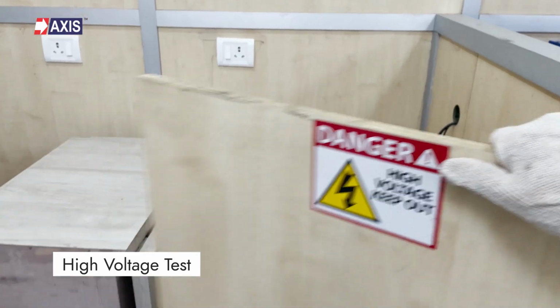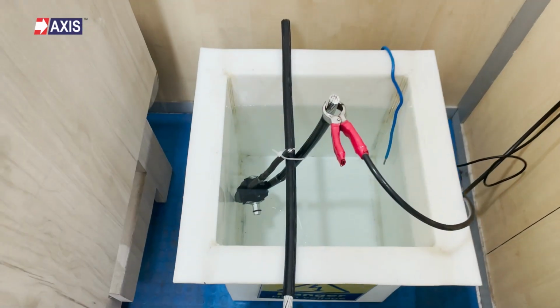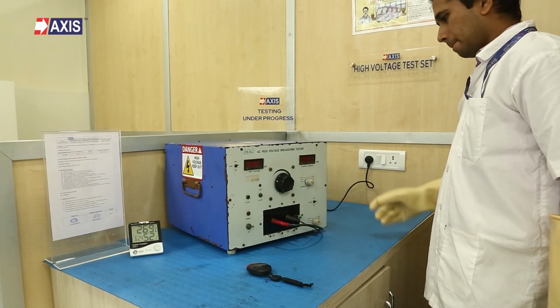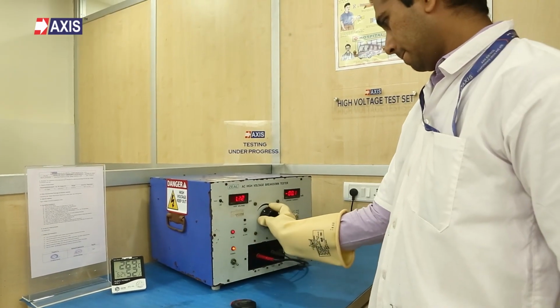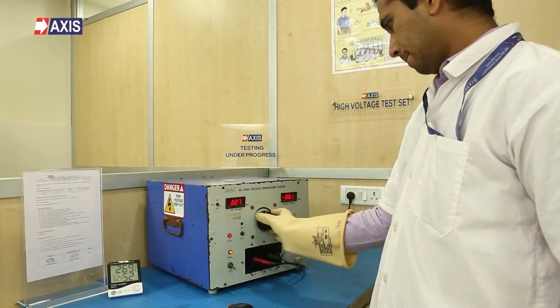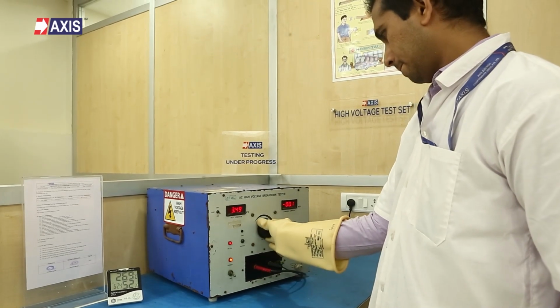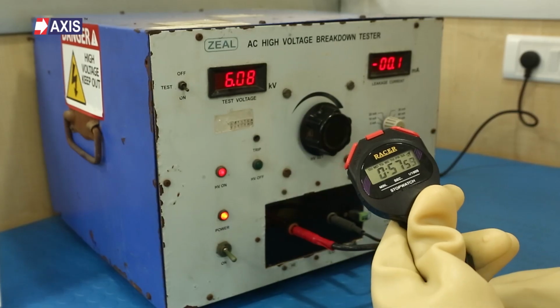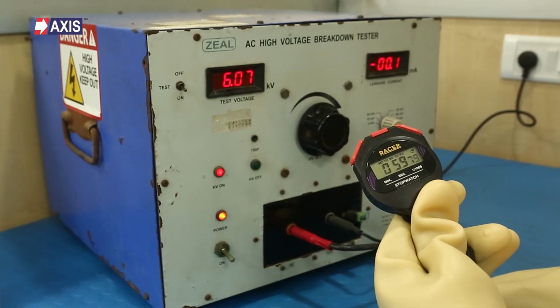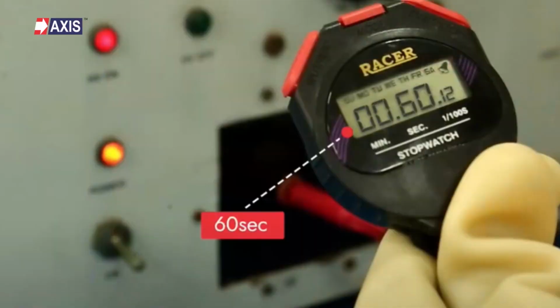Now, test number 3, the high voltage test. This test checks if the insulation material can handle high voltages, especially during fault conditions. If the HV tester trips and the buzzing sound stops before the required time, the sample has failed. This means that the IPC could not sustain the required high voltage level. As you can see here, our HV tester did not trip and held a high voltage of 6 kV for 60 seconds. This tells us that our connector can handle high voltage levels during fault conditions.